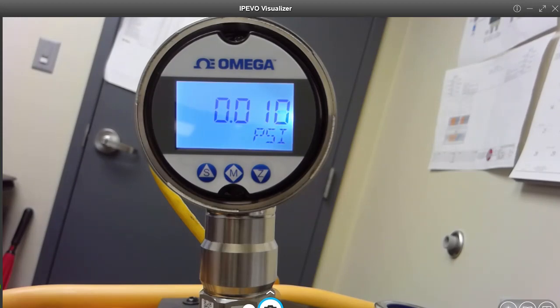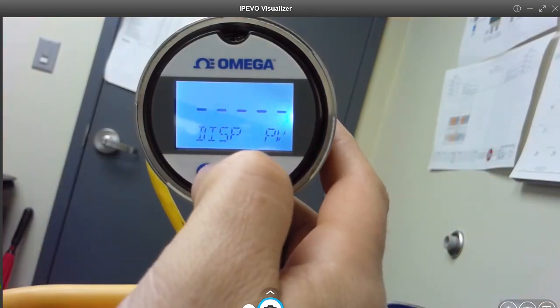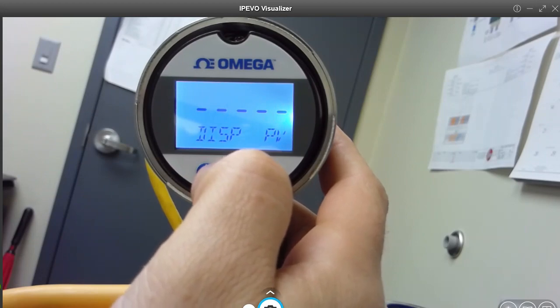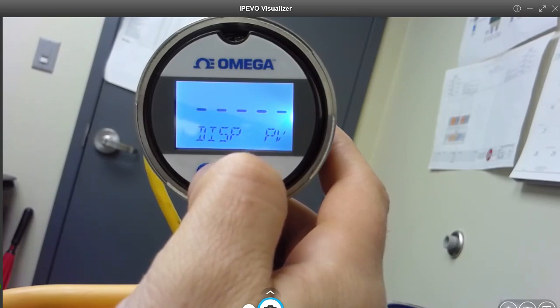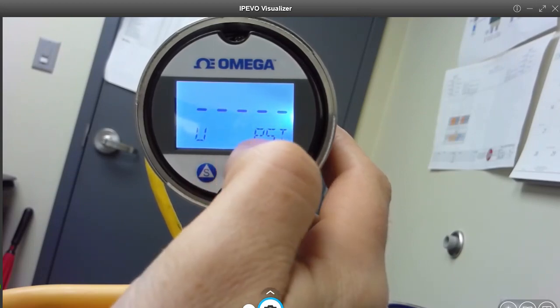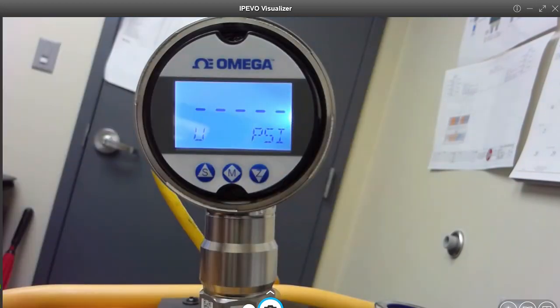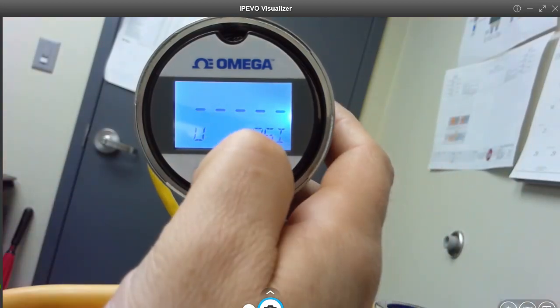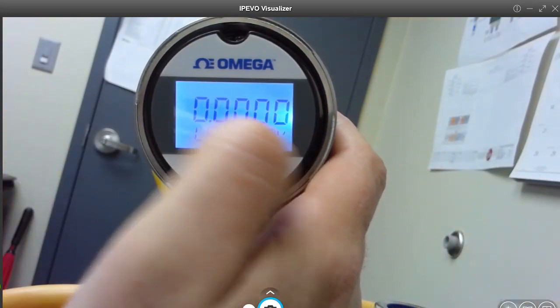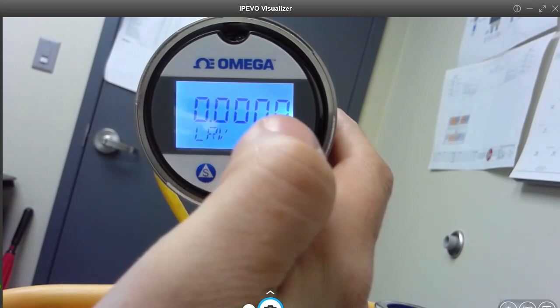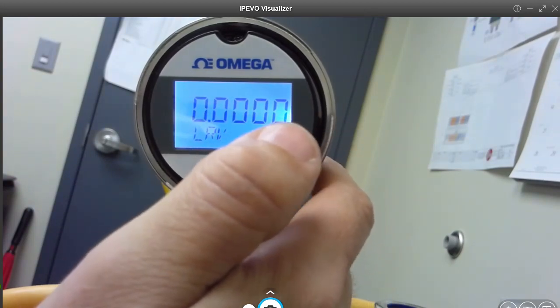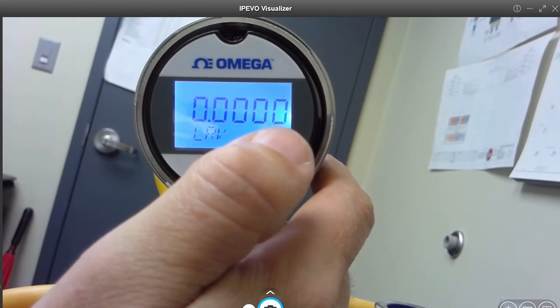We're going to press the menu key and verify that PSI is our display option, and we'll see that our display is PV. We're going to press the menu key again, verify that we have PSI. That's what we're going to be reading. We'll hit the menu button again to verify that the process variable is set to 0. Since we're at a PSI unit, this is 0 PSI.